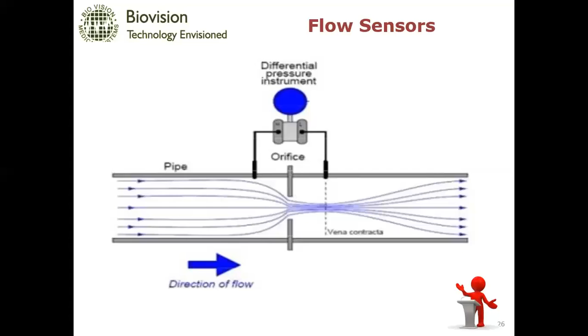So this pressure difference is being measured, and it is a very commonly used flow sensor. It is an external flow sensor which will be used near the patient, very commonly used nowadays because of its easy availability and low cost. So it is a differential pressure based flow sensing technology. So these are the three basic technologies of flow sensing: one being hot wire anemometry, indirect measurement using strain gauge, and the third one is using differential pressure technique.